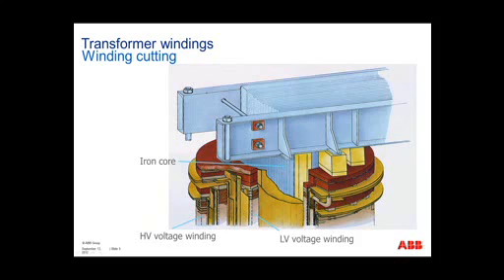Okay. Next one. What overvoltage level in percentage would be a dangerous level at which the transformer should be tripped, and why? Dangerous overvoltage levels will need to be looked at. The transformer comes with documentation that shows you. Let me see if we go back to this slide. It'll show you the capabilities of the transformer, both self-cooled and non-cooled.